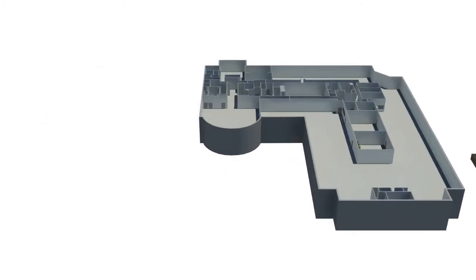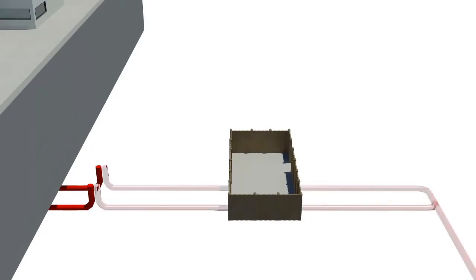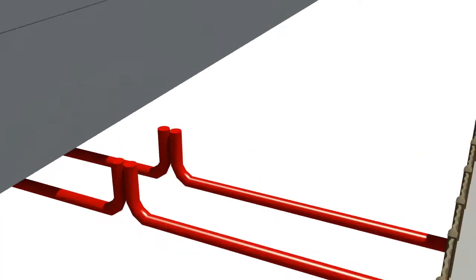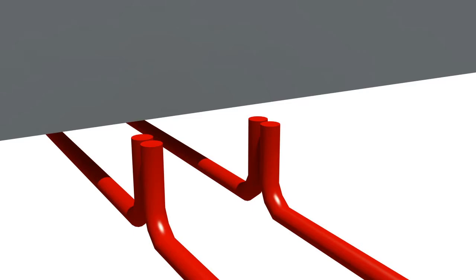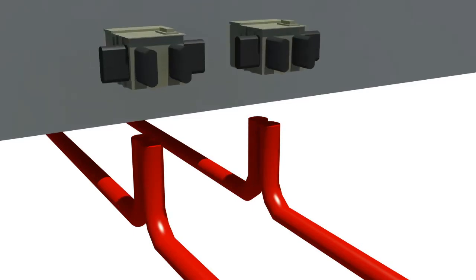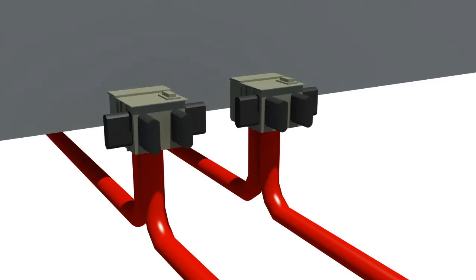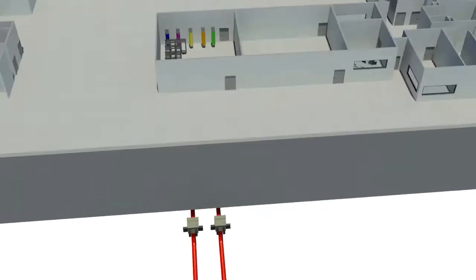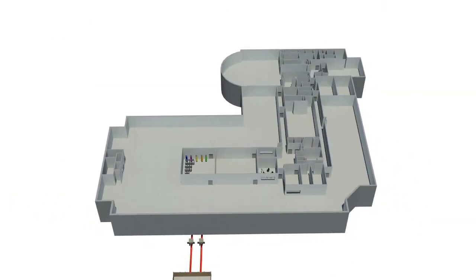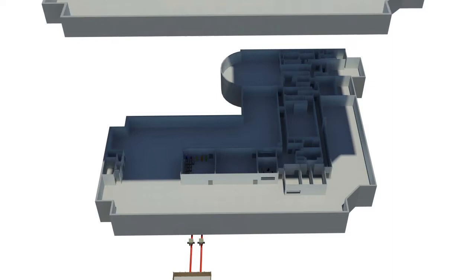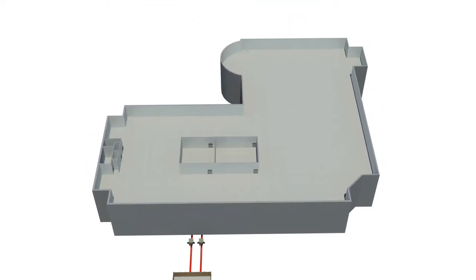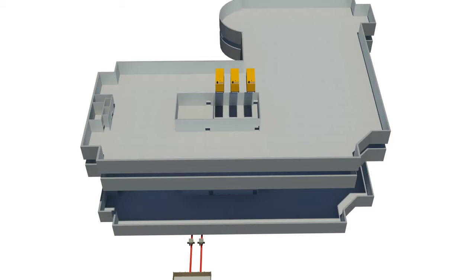Commercial power is delivered to this facility through redundant 4,000-amp A and B power feeds. This power bus configuration is conditioned by power distribution units and 4 500 kVA uninterruptible power supply units. In the unlikely circumstance that commercial power to the site is temporarily disabled, these systems are supplemented by 3 2.2 megawatt diesel generators and 30,000 gallons of diesel fuel on site, which can power the center for as long as needed.